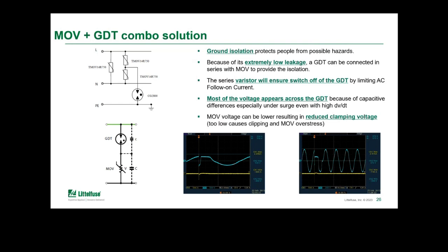Another combination is for applications that require isolation. An MOV typically, in some instances, should not be connected to ground, and there are certain areas of the globe where this is actually not allowed. To get around this and still provide adequate surge protection, use an MOV in series with a GDT, because a GDT has very low leakage and very good isolation.